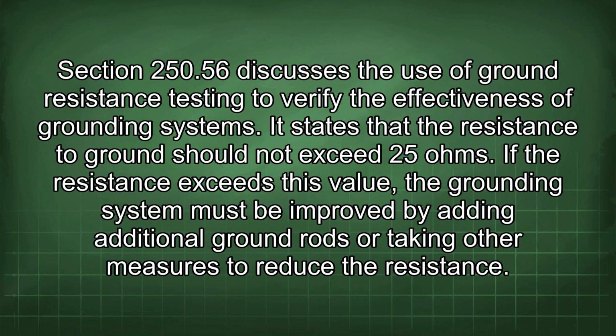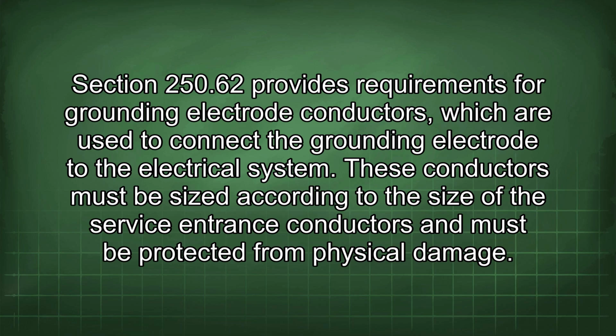If the resistance exceeds this value, the grounding system must be improved by adding additional ground rods or taking other measures to reduce the resistance. Section 250.62 provides requirements for grounding electrode conductors, which are used to connect the grounding electrode to the electrical system.